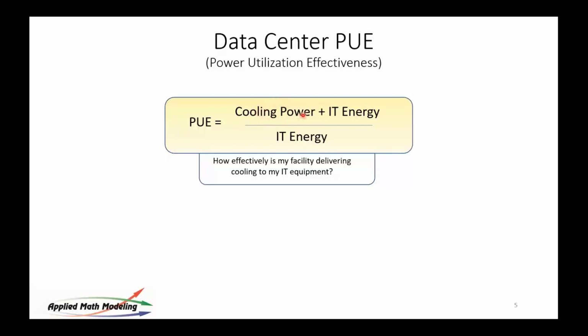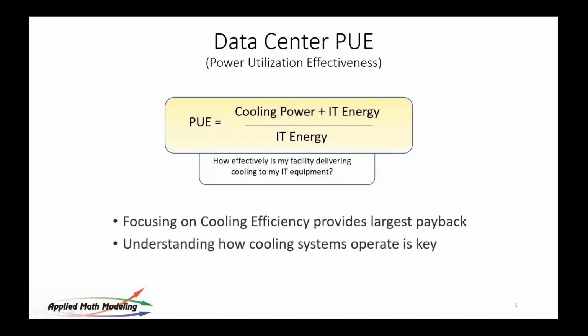That's the dominant parameter in that numerator, cooling power. And then you have IT energy and IT energy. So if you focus on the cooling efficiency, if you focus on these two, and I've presented this in earlier webinars, where I've focused really on the ratio of these two things. And that's exactly what ASHRAE 90.4 did.